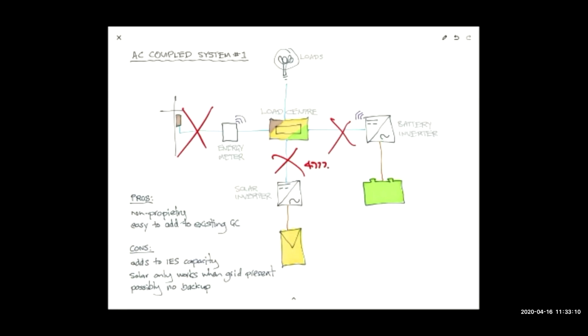So both of these will turn off. This system, as I've drawn it, 4777 Part 2 is our grid protection standard. Those two ports on those inverters must disconnect from the grid within 2 seconds. So you might think, well, hang on Glenn, what's the use of having a battery if when the grid fails you have no power? Well, it's not all about having power when the grid is operational. Often, or most of the time, it's about self-use of renewables. There are systems out there that will only work when the grid's present and provide no backup, but when the grid is present, they're providing a way of storing surplus solar and allowing the customer to consume it at another time, at night time or when there is a deficit. So it's about self-consumption. But there are ways of adding backup to this design, which I'll get onto.